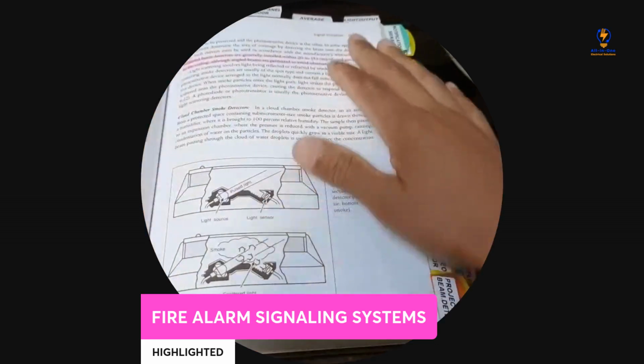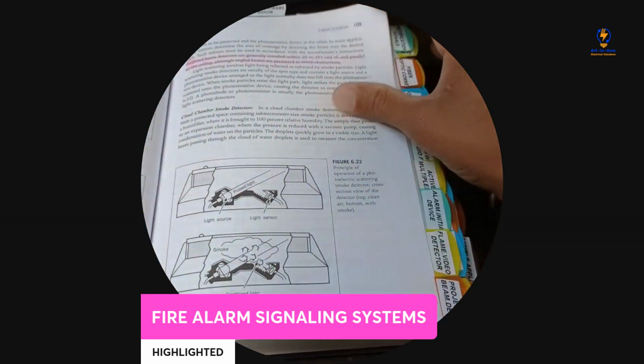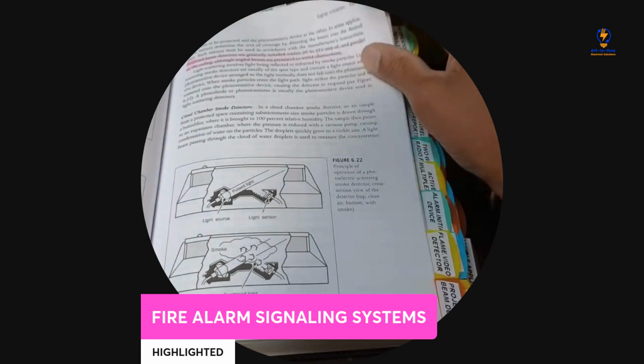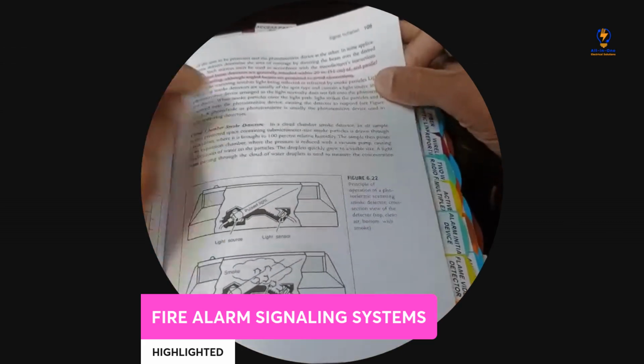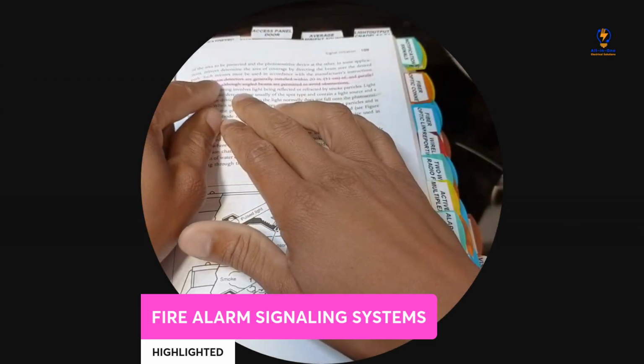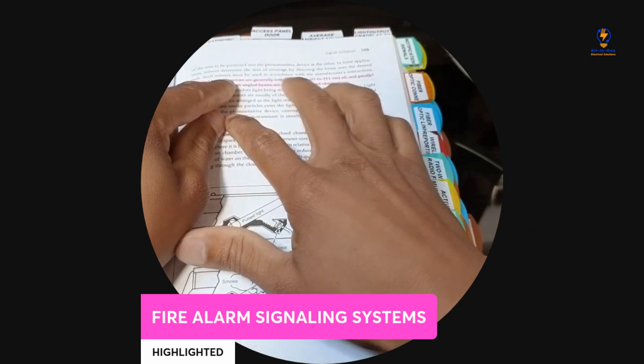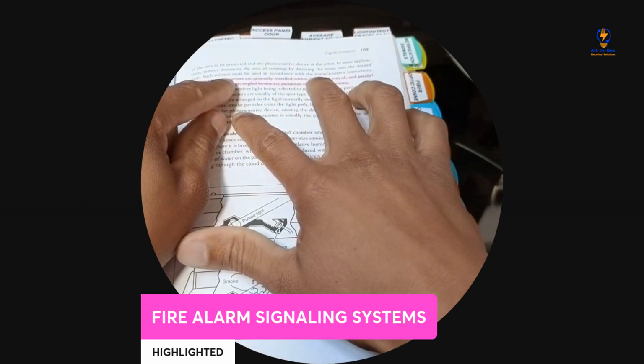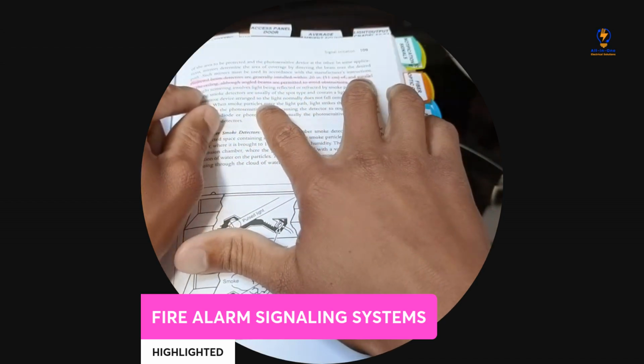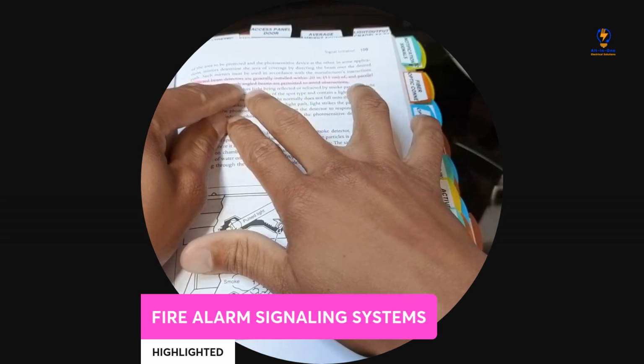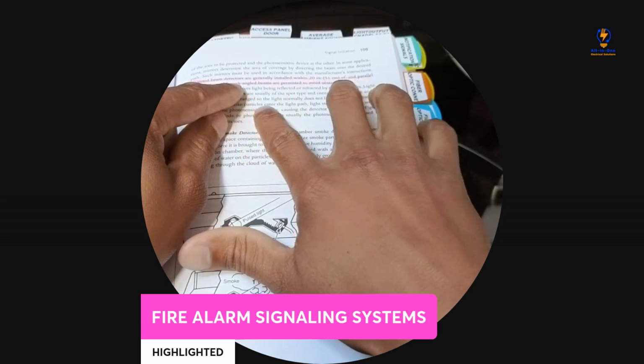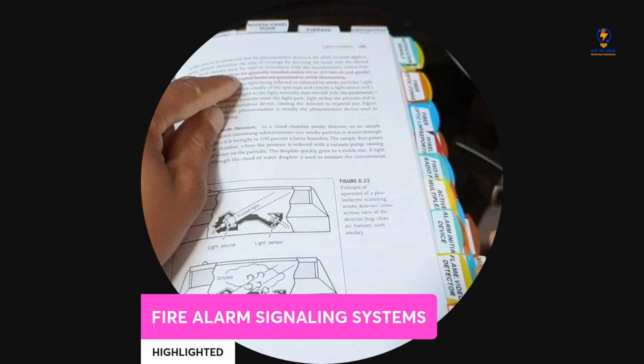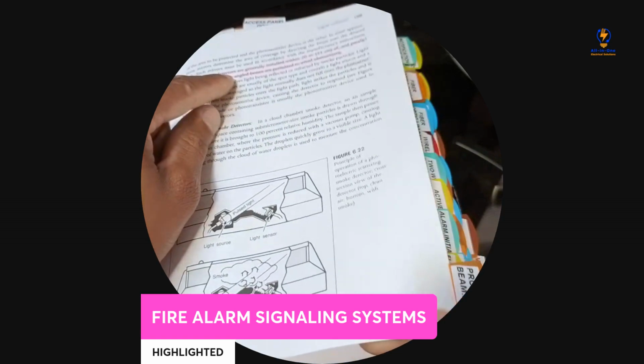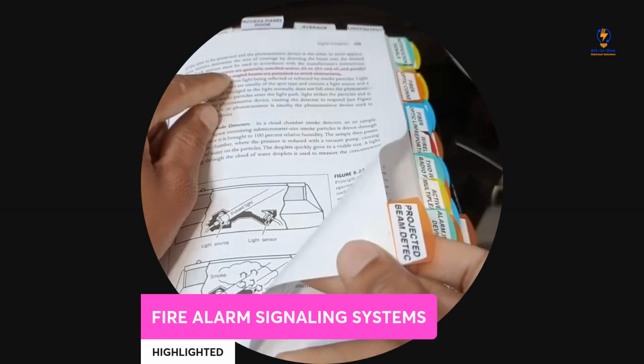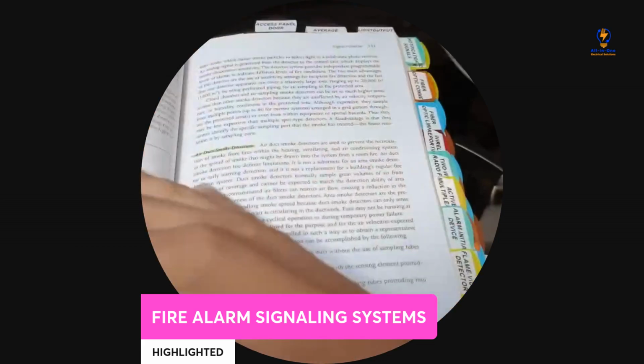And then in page 109, this paragraph, the last two lines: projected beam detectors are generally installed within 20 inches and parallel to the ceiling, although angled beams are permitted to avoid obstructions. 20 inches. I put a tab in here, projected beam detector, as a tab in page 109.